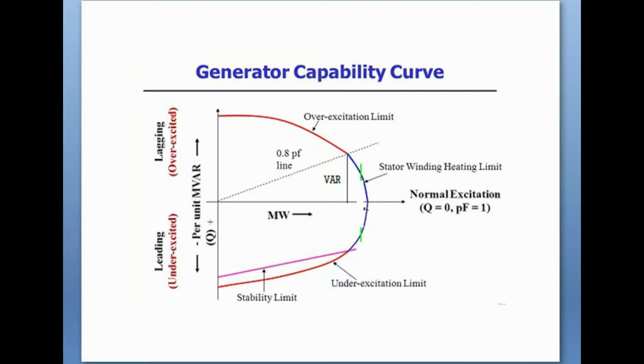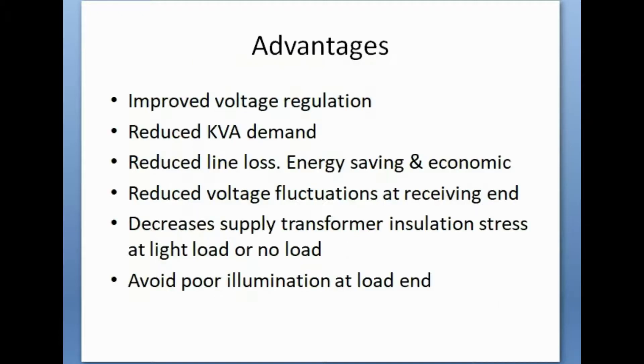Now we will discuss the advantages of power factor improvement using shunt capacitors. The first advantage is improved voltage regulation. If we connect the capacitor bank at the load end, then the sending end voltage and receiving end voltage variation will be less. At light load or no load condition, voltage regulation is normally higher, but if we arrange for capacitor banks for power factor improvement, then voltage regulation will be reduced and the voltage profile will be improved at the receiving end.